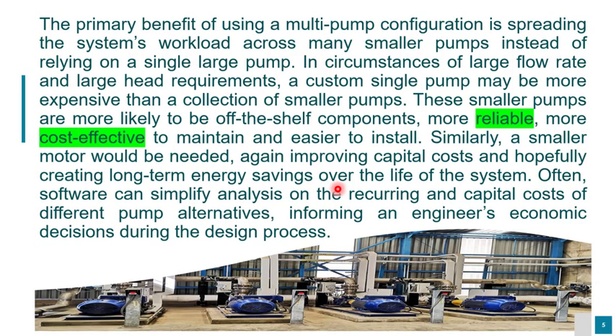The primary benefit of using a multi-pump configuration is spreading the system's workload across many smaller pumps instead of relying on a single large pump. In circumstances of large flow rate and large head requirements, a custom single pump may be more expensive than a collection of smaller pumps. These smaller pumps are more likely to be off-the-shelf components, more reliable, more cost-effective to maintain, and easier to install. Similarly, a smaller motor would be needed, improving capital cost and hopefully creating long-term energy savings over the life of the system.